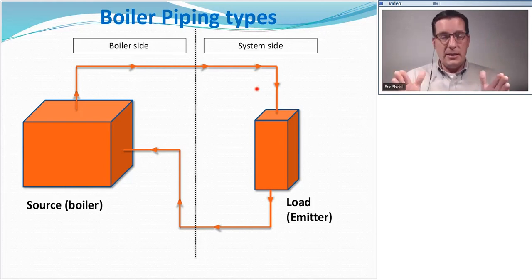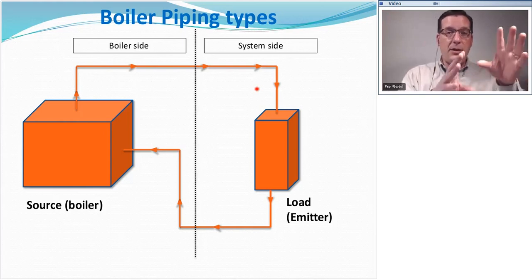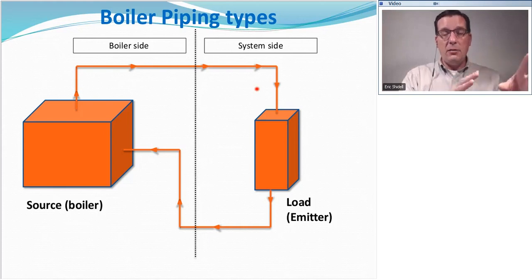Earlier I said it's easy for a technician to put the blinders on and get pigeonholed in the boiler room and only focus on the boiler side. And the boiler side is, of course, very, very important. But equally important is the system side. So the boiler side contains the boiler itself, usually the circulator pumps, usually the controls, and what's called the near boiler piping. Out there in the system, however, is the other half of the whole assembly. And what is happening out here in the system can also affect what's happening in the boiler room. And if you don't leave the boiler room and go out into the rest of the building and look at the system, you could be missing the whole source of the problem.